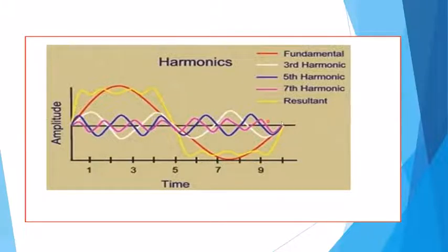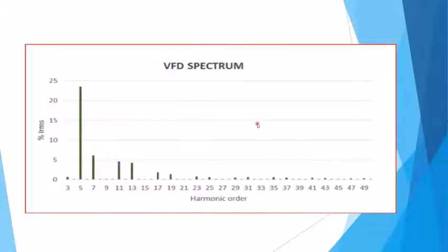So this has caused some issues and concerns with the power companies, because noisy power ends up chewing up more power. So this shows like the harmonic order that you typically see on a 3-phase. You have your fundamental power at 1, and then you have it at 3 or 180 hertz, or 3 times 60, 5 times 60, 7 times 60. And typically the 5th harmonic is one of the higher ones that you have to be cautious of.